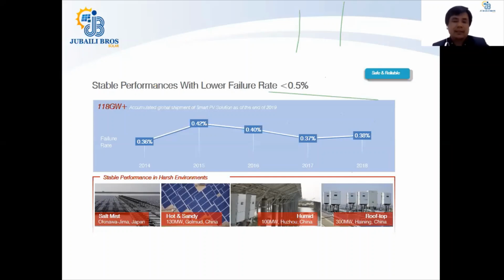The reliability comes out of the different kinds of testing in manufacturing, and Huawei has been testing in different real-time scenarios such as salt mist in Japan, which is a location having high salty air, hot and sandy weather, humid weather, and rooftop installations with no shade. But such projects where you're not putting a shade on your inverter are not recommended. We would suggest that you use shade on top of your inverter when you're installing it outside and the inverter is exposed to sunlight.